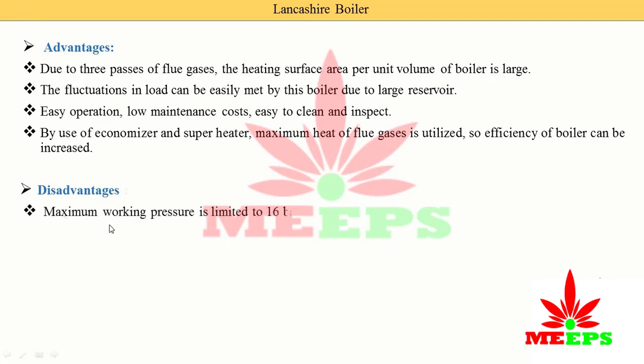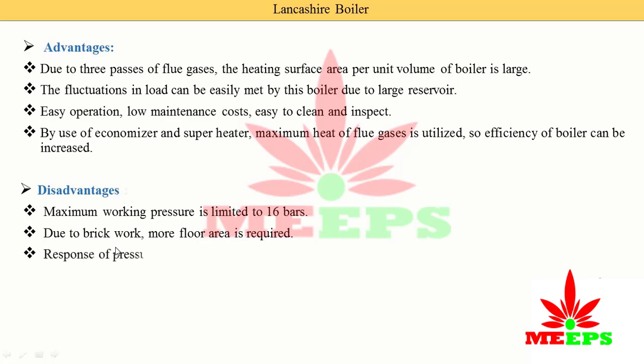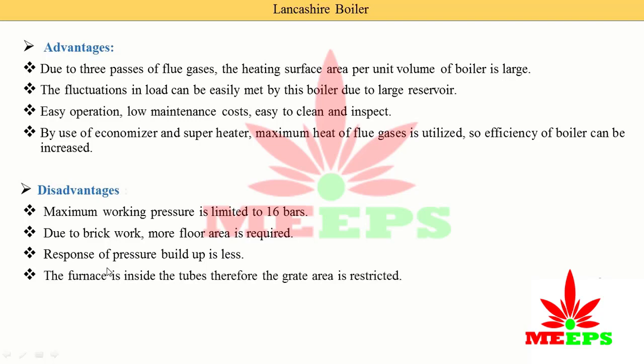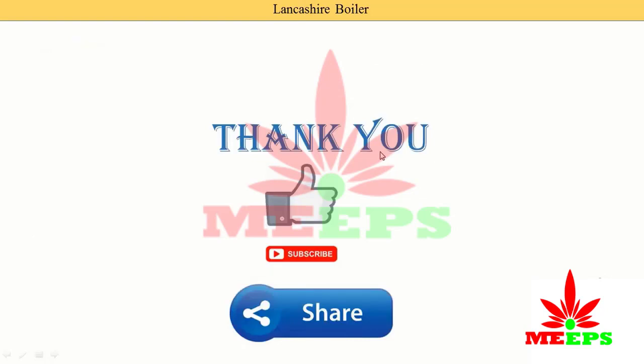Disadvantages of the Lancashire boiler: the maximum working pressure is limited to 16 bar. Due to the brick work, more floor area is required. Response for pressure build-up is slow — more time is required to achieve 16 bar pressure. The furnace is inside the tubes, which restricts the grate area, limiting the combustion area for fuel. This limited furnace area also contributes to the longer time needed to build up pressure. Thank you for watching — please like the video, subscribe, and share with your friends.